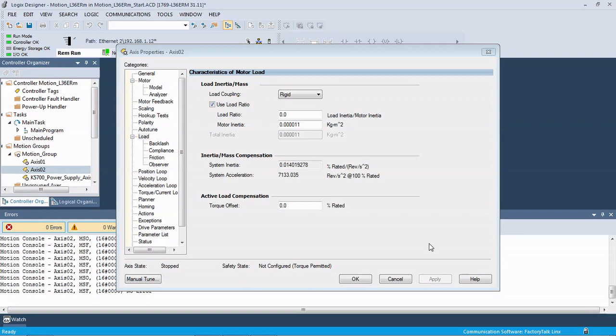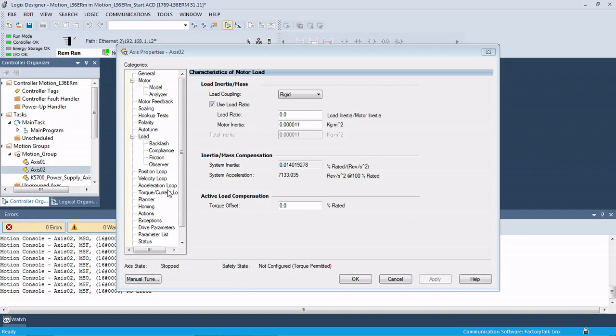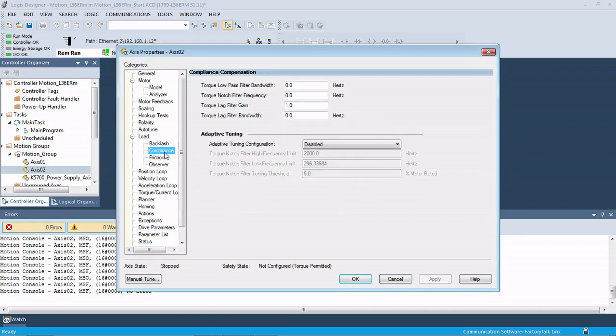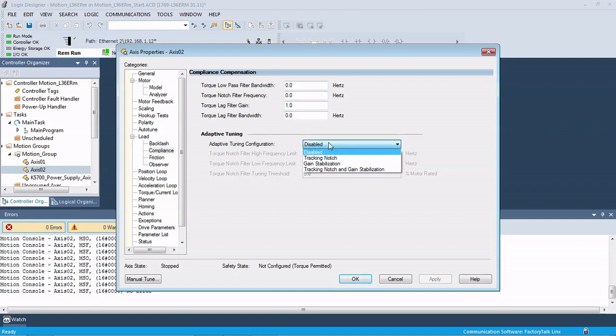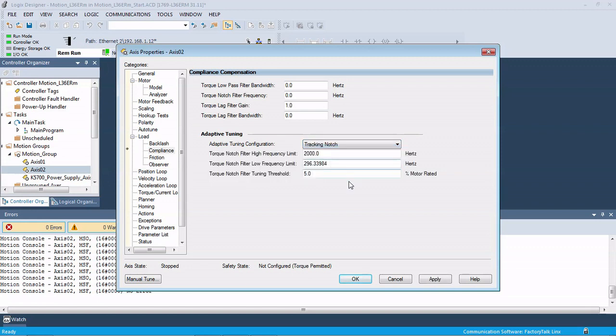So that sound we got was a little more high-pitched than the other grinding sound, and that's because of the compliance in this machine - there's a resonant frequency in this axis. The next step is to set up the tracking notch filter. Normally what you would have to do is pull out a phone or some sort of sound measuring device, find out what that frequency was, go into your setup here, and you would need to put a notch filter at that frequency to get rid of it. But any time there are changes in the mechanical design or system, you'd have to change that notch filter.